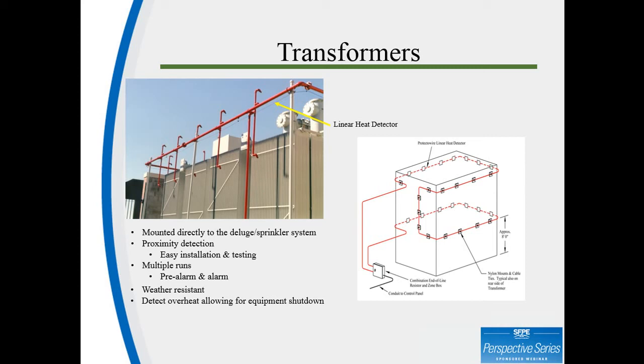The second means of protecting a transformer is to place the detector on the deluge piping around the top of the transformer. Prior to using this installation technique, however, you will want to check or verify with your local AHJ, authority having jurisdiction, to verify if they'll allow the detector to be placed on the sprinkler or deluge piping. The interpretation of NFPA 13 can vary significantly with each jurisdiction.